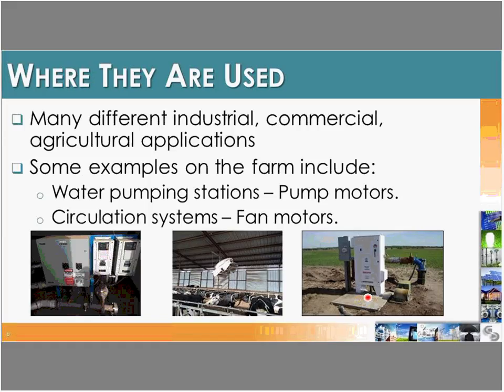Question: will a VFD control an existing motor or do we need a new motor? It depends. If you have a single-phase motor, you would have to change it to a three-phase motor — a VFD will not operate a single-phase electric motor. However, if you currently have a three-phase electric motor, a VFD does have the capability to control that motor without having to change it.